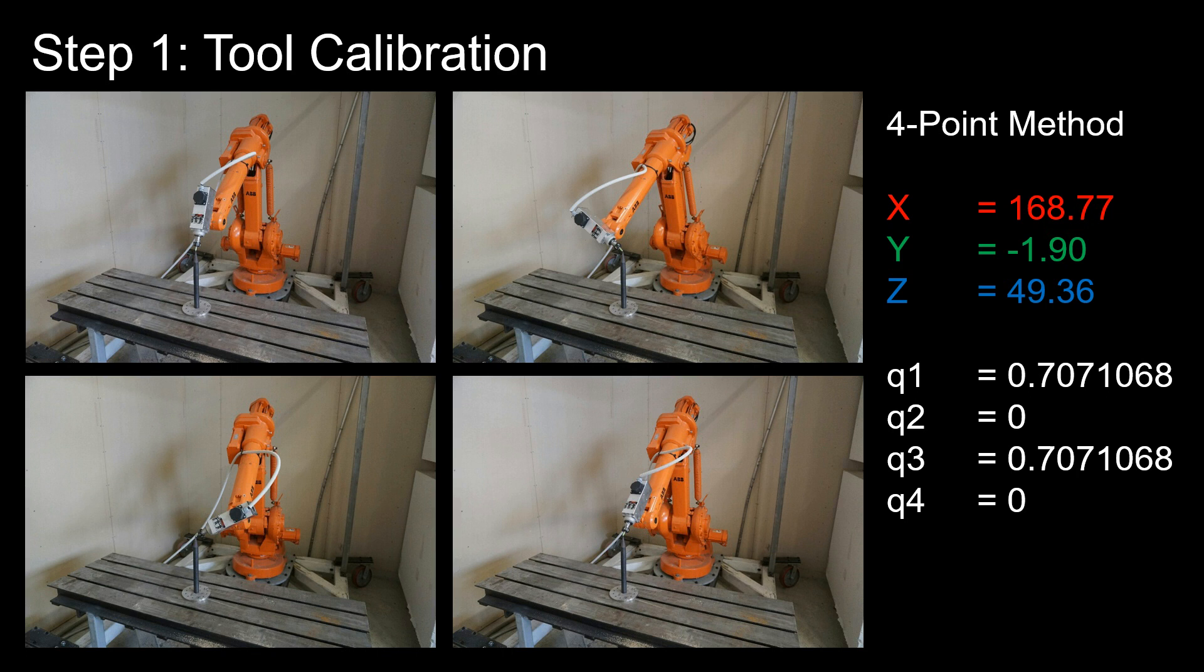It should also be said that to do this, it's actually enough with three points. So having a four-point method, we have an extra measurement. And that extra measurement can be used by the controller to give an accuracy of your calibration. So typically, you should aim for an accuracy result of 0.3 mm or better.